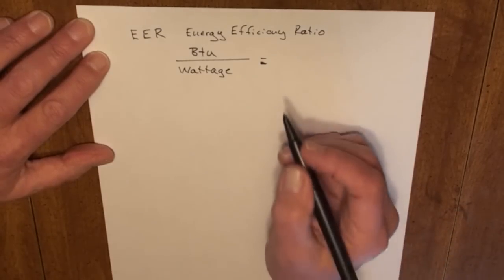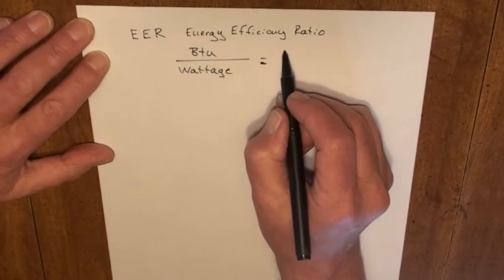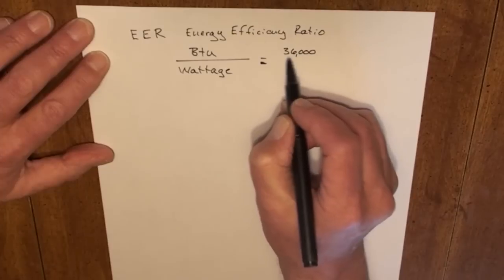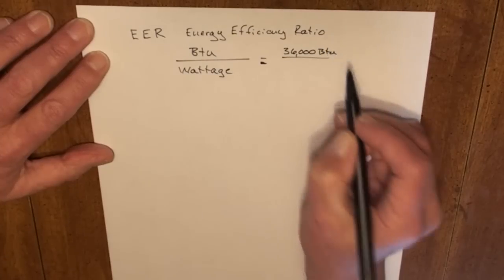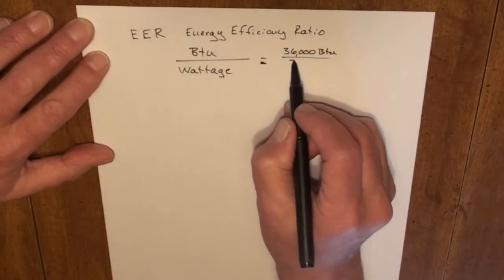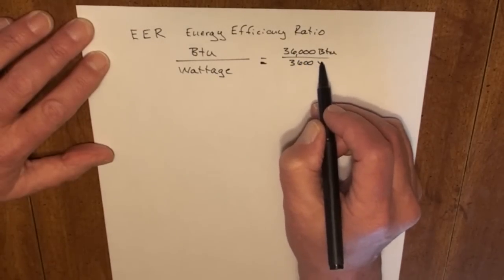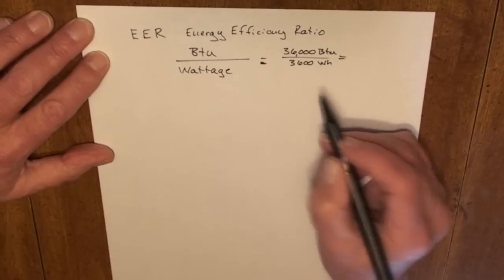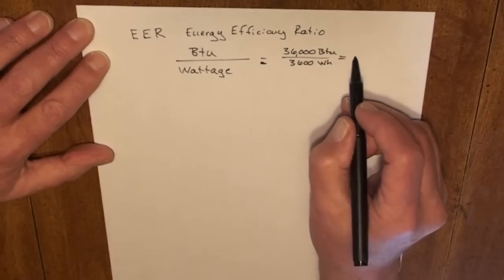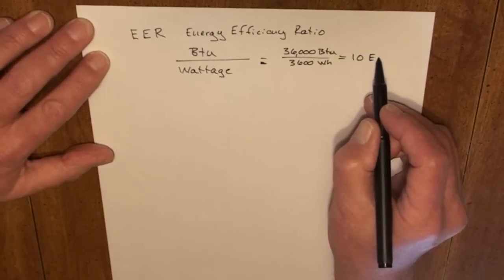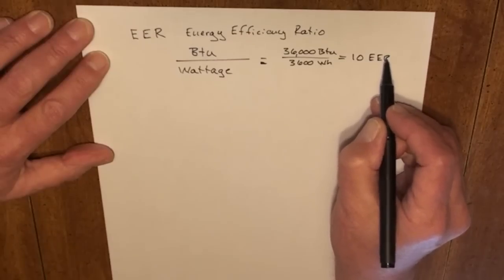For example, if I had a 36,000 BTU air conditioner, a 3-ton air conditioner, and it used 3,600 watts per hour, 3,600 divided into 36,000 would equal a 10 EER unit.